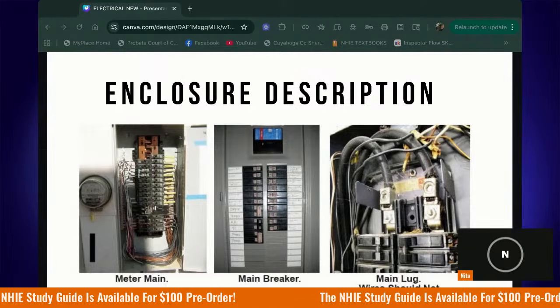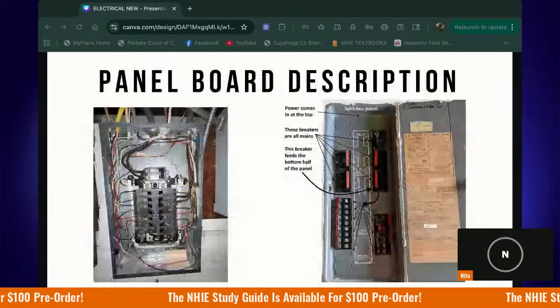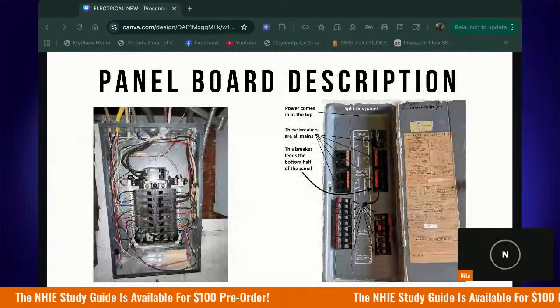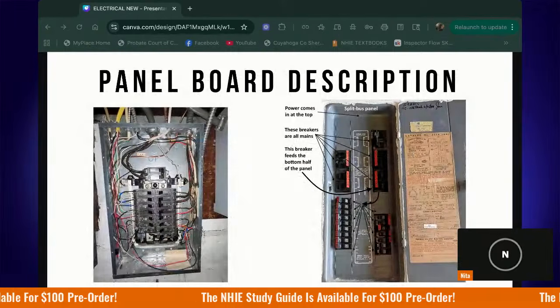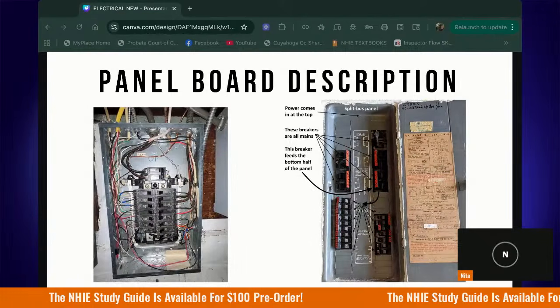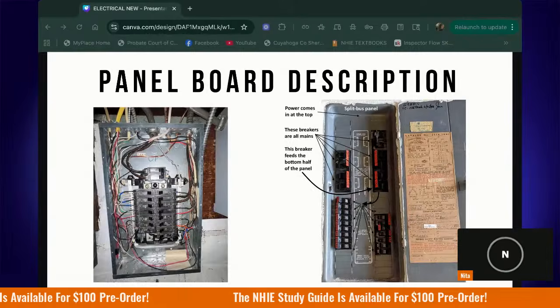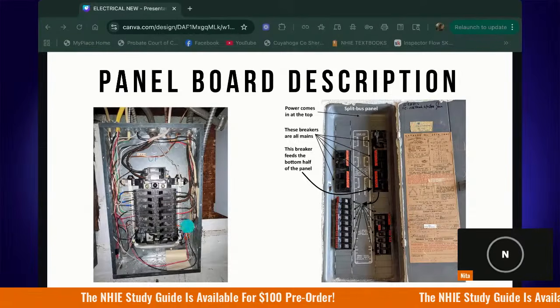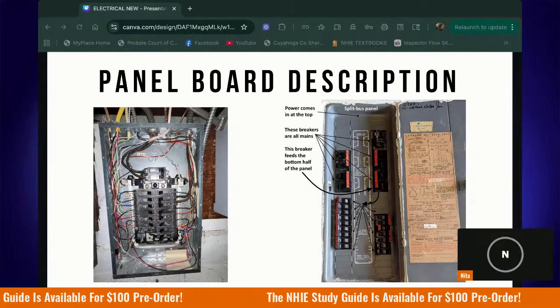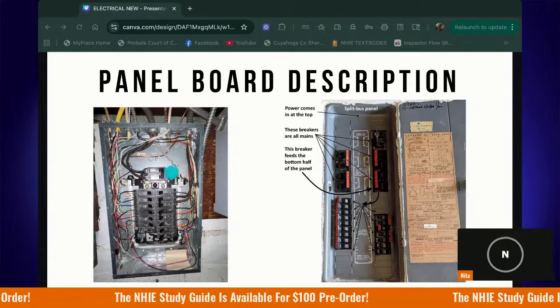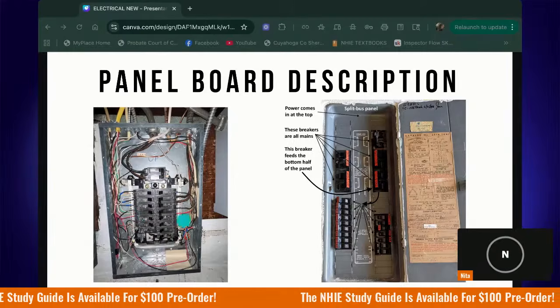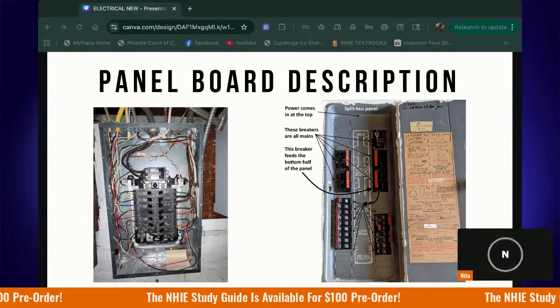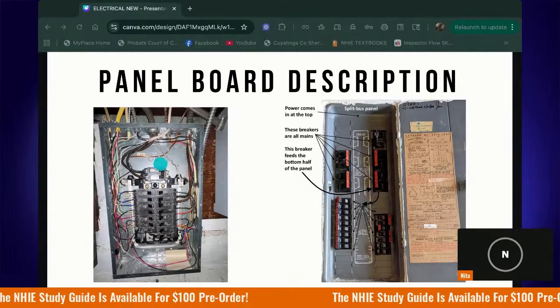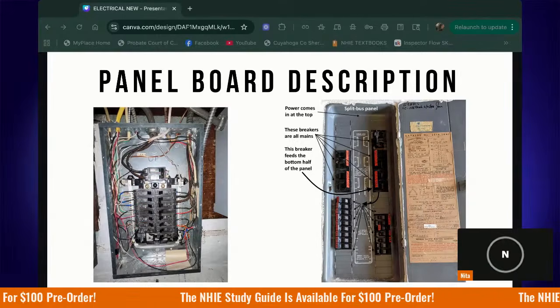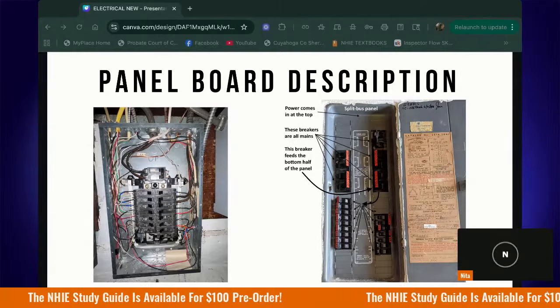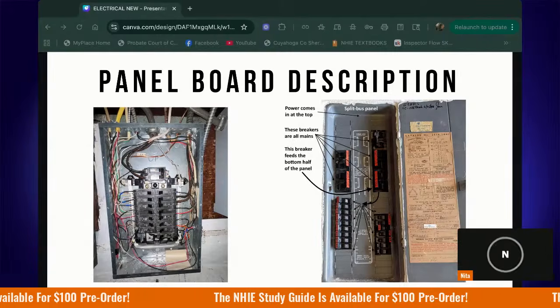Okay, so these are our enclosures. And then we have our panel board again. So this is the main distribution point for our electricity. Okay, we have single bus panel boards, which are again most common today. This one on the left, where the main breaker again shuts off all of the power. So this up here is the main breaker, and it can control the power to all of the circuits. You can kill it in one motion. That breaker is again typically, it has to be a minimum of how many amps? 100. That's correct. A minimum of 100.